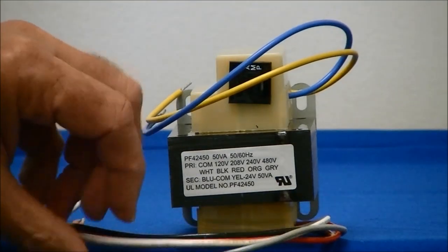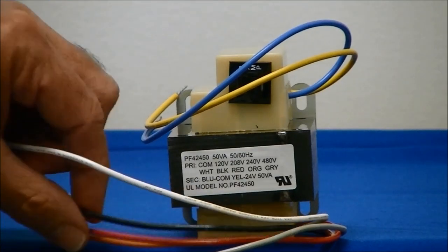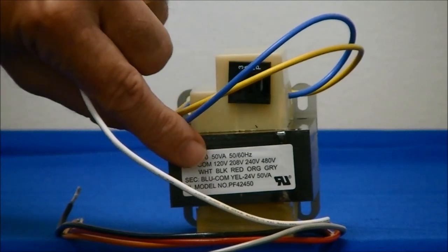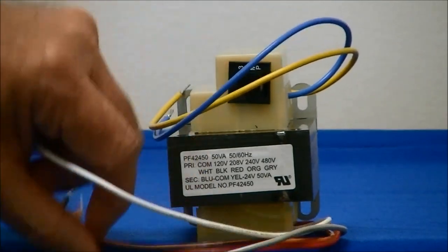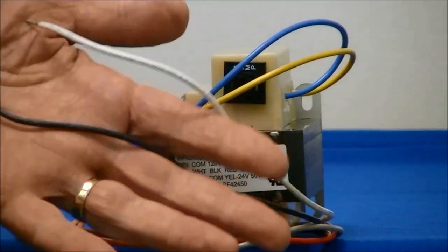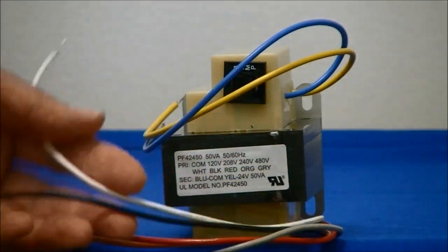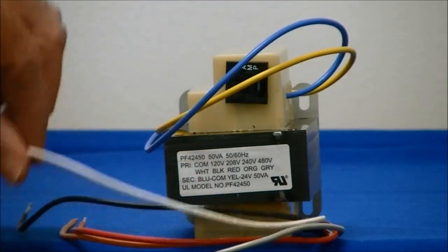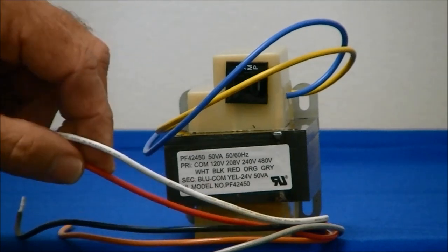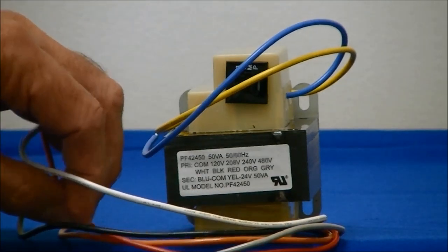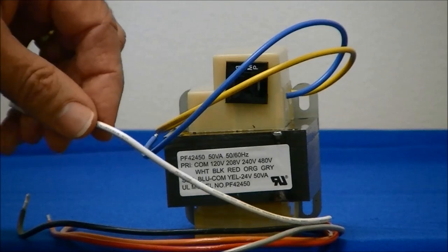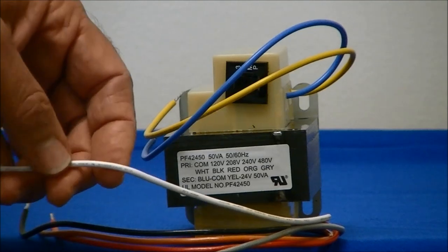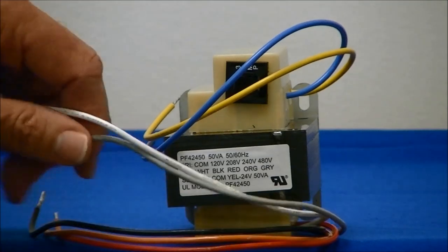So for the primary voltages, utilizing it on 120 volt, we connect the white lead to one side of the power, and the black lead to the other power lead. To operate on 208 volts, connect the white and the red to the power. For 240 volts, we connect the white and the orange to the power. And for 480 volts, the white and the gray to power.